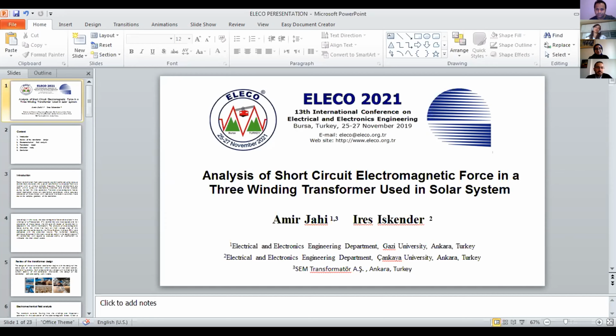Power transmission from solar systems to the grid is achieved using step-up transformers. Generally, this type of transformer is energized from an inverter with or without variable frequency. Power transformers deal with a variety of mechanical, electrical, and thermal stresses during normal lifetime operation. Transient electromagnetic forces cause mechanical stress on transformer parts, where accurate calculation of these forces with traditional methods is extremely hard due to the complex geometry of the transformer.